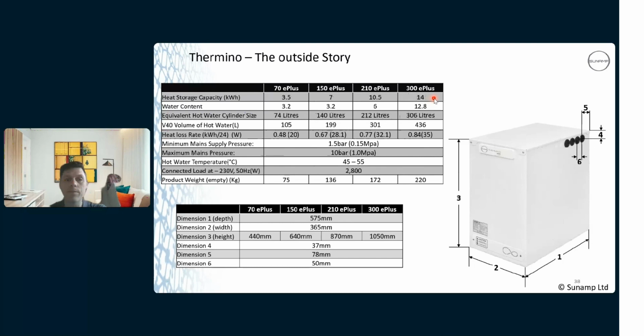Then you go to your water content of the heat exchanger, that's the water content of the heat exchanger at any one time. So obviously less than 15 litres, you don't have to comply with Legionella. Happy days. Our comparable cylinders relating to our heat batteries.